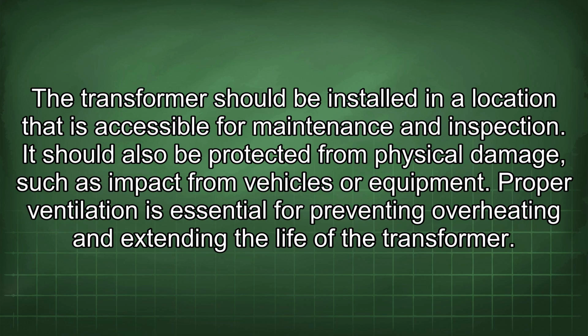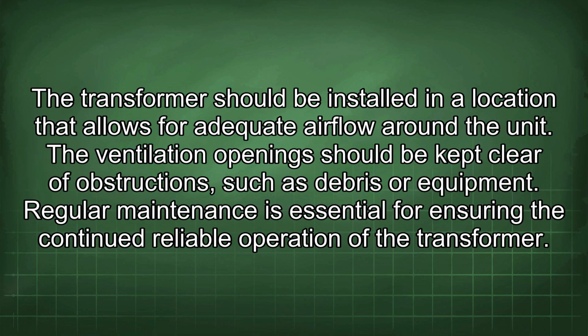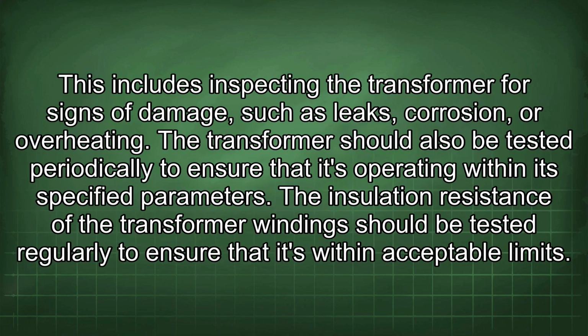Proper ventilation is essential for preventing overheating and extending the life of the transformer. The transformer should be installed in a location that allows for adequate airflow around the unit. The ventilation opening should be kept clear of obstructions such as debris or equipment. Regular maintenance is essential for ensuring the continued reliable operation of the transformer. This includes inspecting the transformer for signs of damage such as leaks, corrosion, or overheating. The transformer should also be tested periodically to ensure that it's operating within its specified parameters.